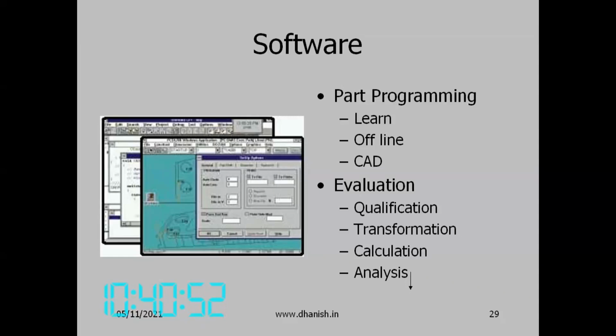Then CMM software has the function of evaluation, which again has several parts. Evaluation is the conversion of the coordinate data into various dimensions. First is qualification. If you recall the stylus, the point of contact is not the center of the stylus. So in which direction is the stylus contacting the workpiece? That has to be determined. So the vector has to be found out and the stylus diameter compensated. That is the first step. For that, you need to know the position of the stylus and its diameter so that it can be compensated. To facilitate that, we have the qualification operation.